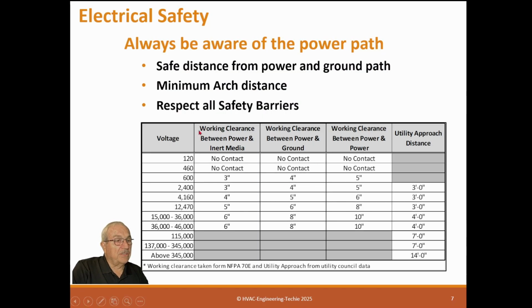So here is the data. The working clearances are from NFPA 70E, and the utility approaches are from the Utility Council data. So these are the different data. Here are the voltages, and this is the working clearance between power and inert media. This is the working clearance between power and ground. This is the working clearance between power and power. If you have 120 volts, it means there's no clearance. Just don't let them touch. Don't touch it, and don't let it touch anything else that's grounded.